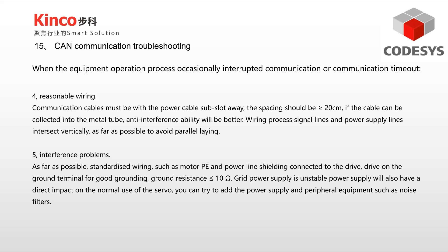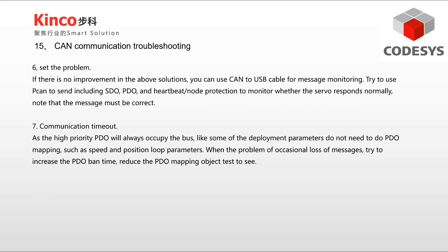Regarding interference problems — as much as possible use standardized wiring, such as connecting motor PE and power line shielding to the drive, ensuring the drive ground terminal has good grounding with ground resistance less than or equal to 10 ohms. Unstable grid power supply will also have a direct impact on normal servo use. You can try adding noise filters to the power supply and peripheral equipment. If none of the above solutions work, you can use a CAN-to-USB cable for message monitoring, and try sending messages including SDO, PDO, and heartbeat/node protection to monitor whether the servo responds normally.